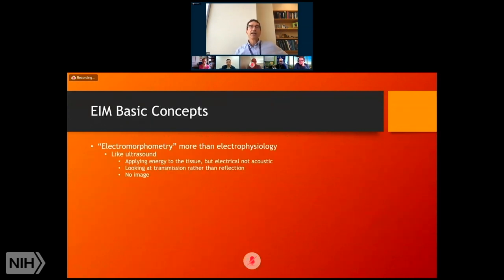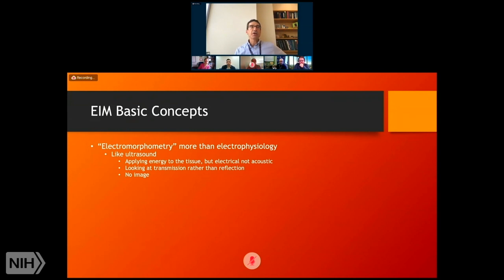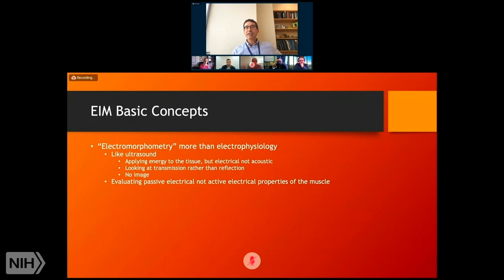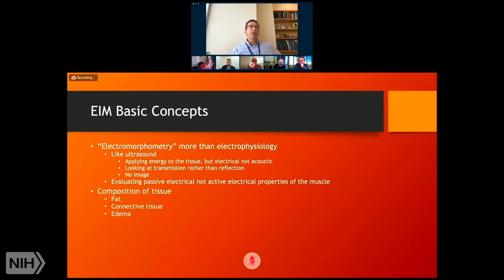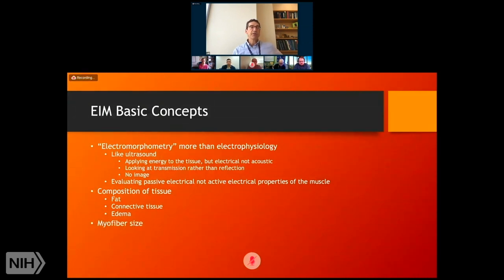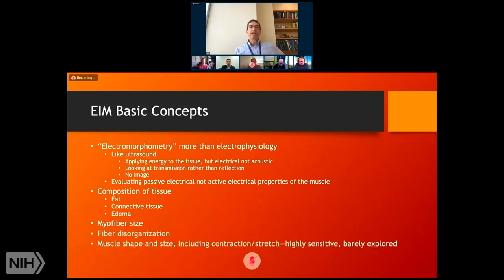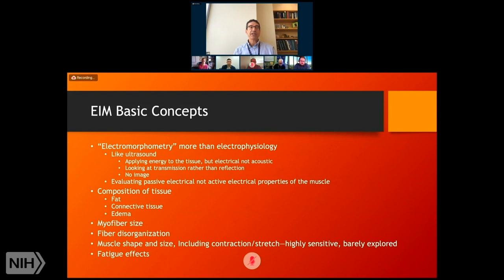I think of EIM more as electromorphometry than electrophysiology — like ultrasound, you're applying energy to the tissue but it's electrical not acoustic, looking at transmission rather than reflection, and not really focusing on producing an image. You're evaluating the passive electrical properties of the tissue. You can look at composition in terms of fat, connective tissue deposition, or edema; myofiber size — we can be pretty good at predicting myofiber size just based on impedance parameters; fiber disorganization; muscle shape and size including contraction, stretch — anything that changes the size or shape of the muscle changes the impedance. This area has been barely explored to date.